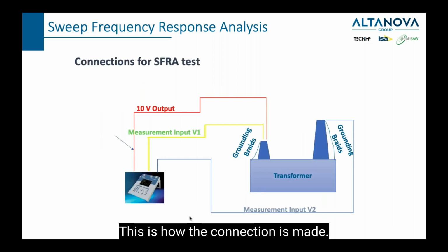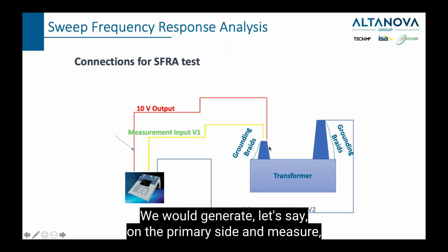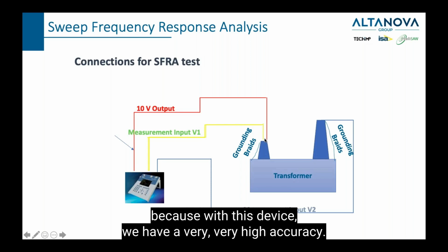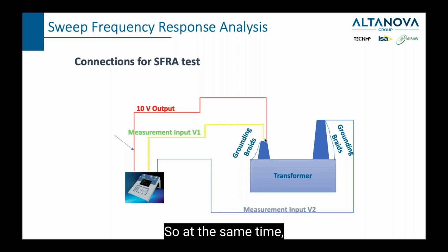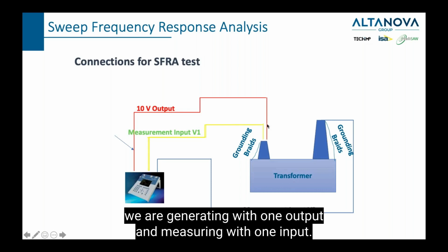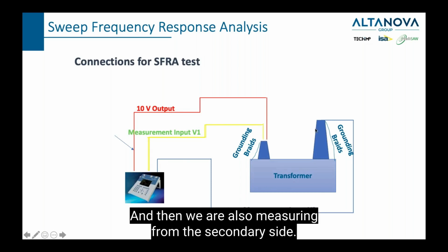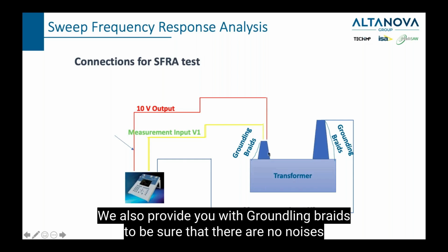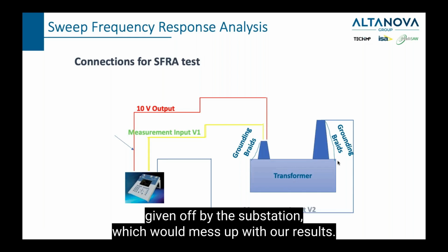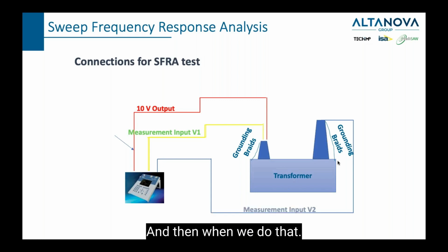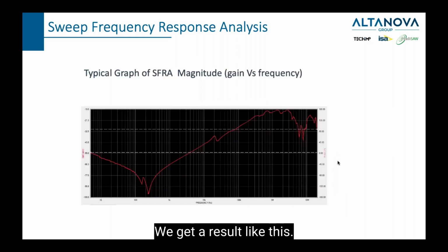This is how the connection is made. We would generate on the primary side and measure, because with this device we have very high accuracy. At the same time, we are generating with one output and measuring with one input, and then we are also measuring from the secondary side. We also provide you with grounding braids to be sure that there is no noise given off by the substation, which would mess up our results. And then when we do that, we get a result like this.